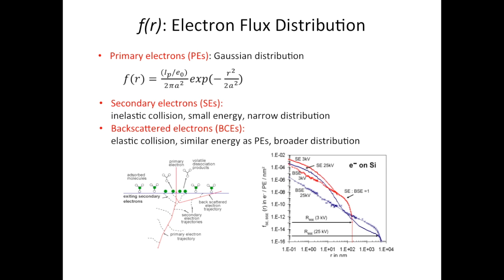We also need to take into consideration the secondary electrons and backscatter electrons. The lower left image shows how these electrons are generated — they are actually generated along the primary beam injection path. But what really counts is the number of electrons that can escape from the bulk to the substrate surface. In the right image, we can see the distribution of both electrons — the red curve corresponds to the secondary electrons, while the blue curves correspond to the backscatter ones.